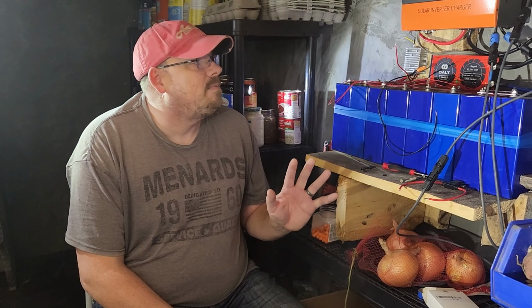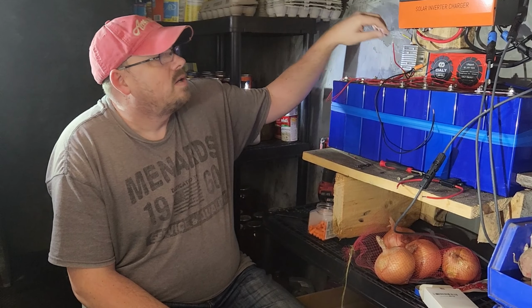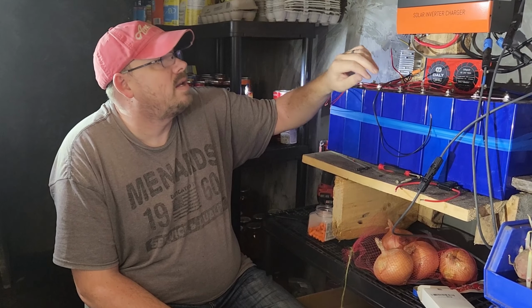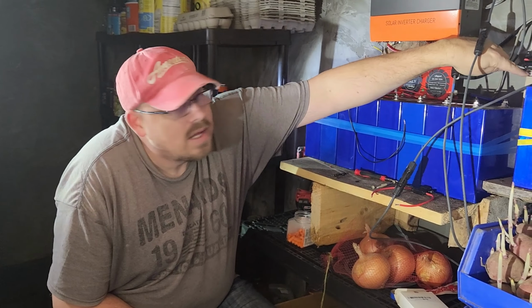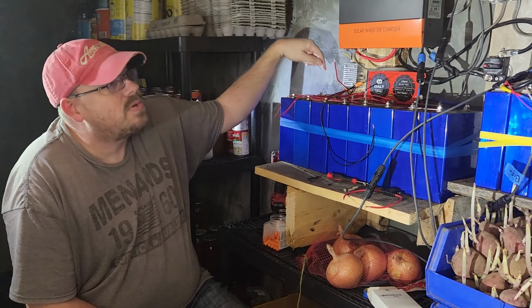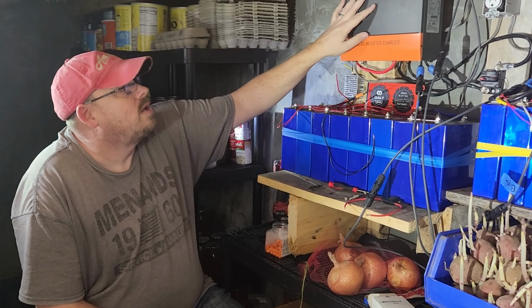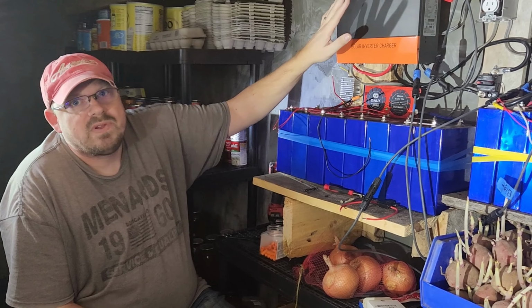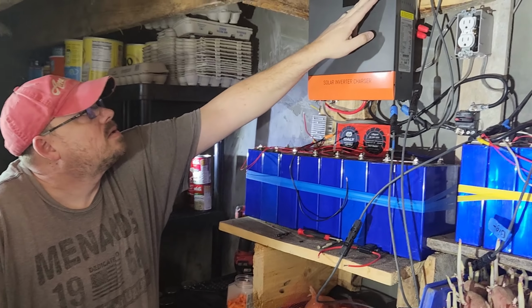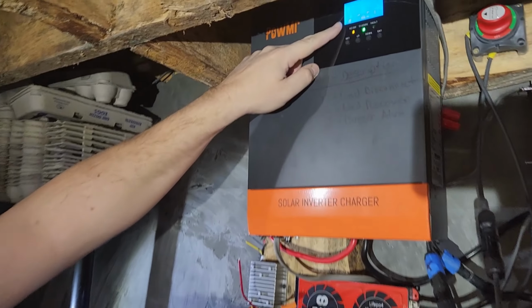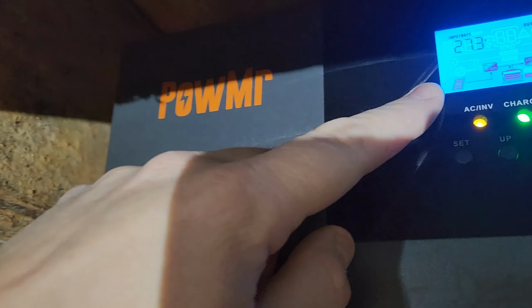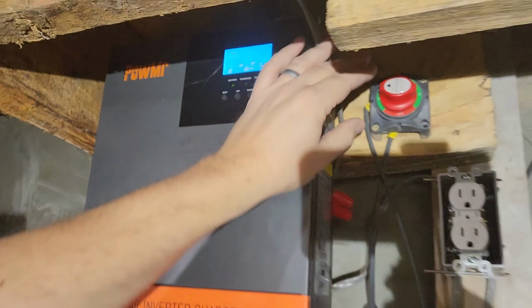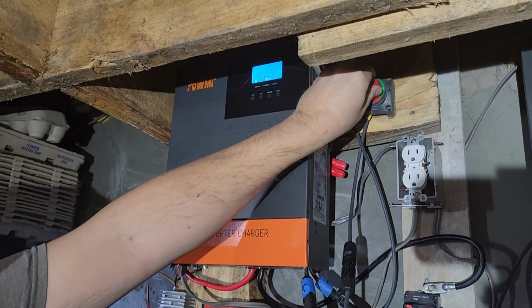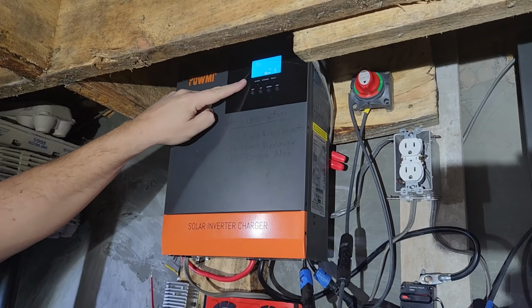Now it's time to connect the converter to the system. To do that, I need to take off these nuts on the cables, so I need to shut the system down first. I'll start by turning off the solar panels. If you look up here, you can see it's indicating it's connected to the solar panels in the corner. I'll now flip my solar panel disconnect, just like a battery disconnect, and you'll see the solar symbol go away.